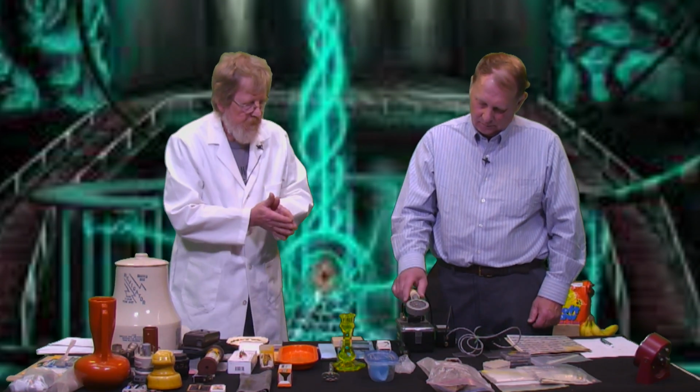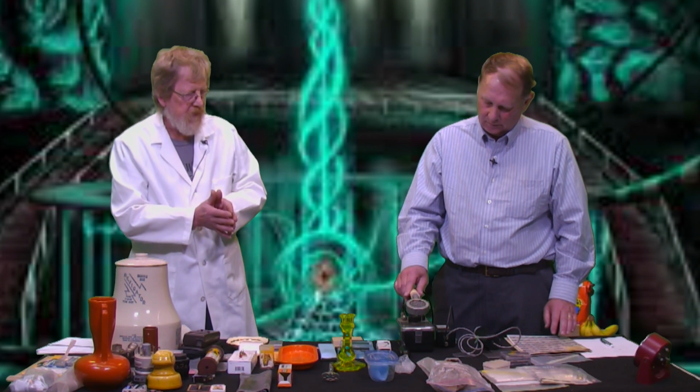The most important part of a Geiger counter is the tube that is inside the counter. It is a thin wall tube. Sometimes parts of it will be made out of mica because you don't want to do anything to shield the tube from the radiation you're measuring. You won't get an accurate count. And it has a conductive outer shell, and it has a wire that runs right through the center. Okay. Those two are hooked up to the circuitry inside the Geiger counter.